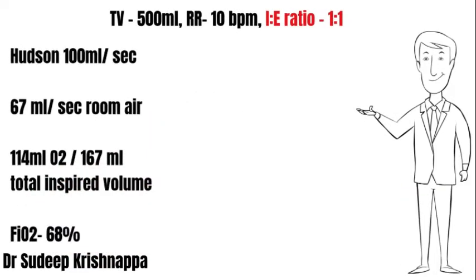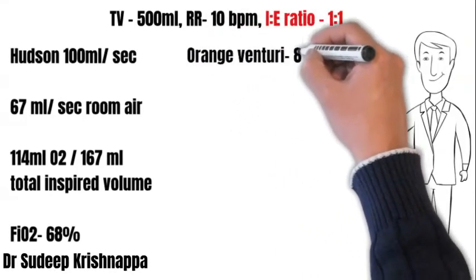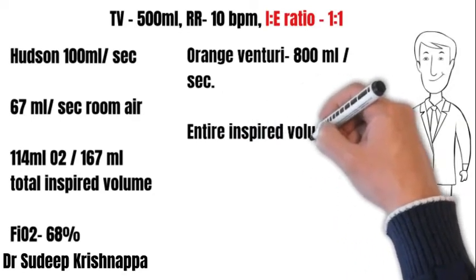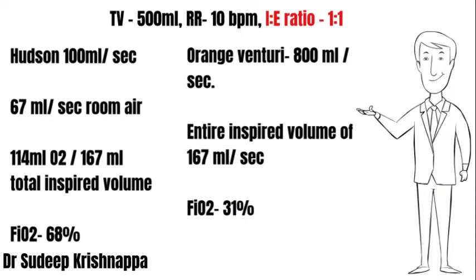In contrast, the orange Venturi generates 800 mL per second flow, so even in this scenario the entire 167 mL per second is met by the flow generated by the Venturi, with no need for further entrainment of room air. The FiO2 remains at 31%.